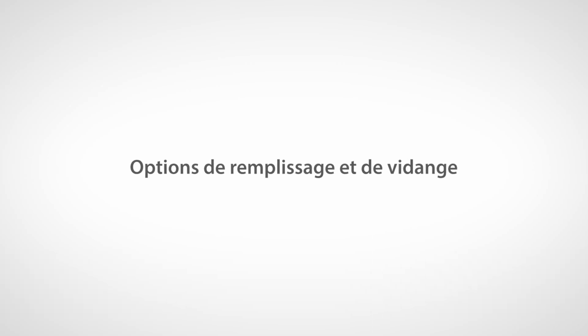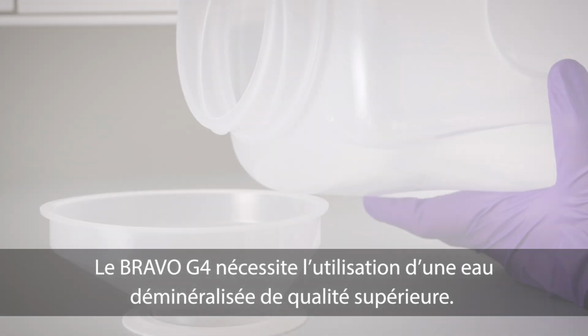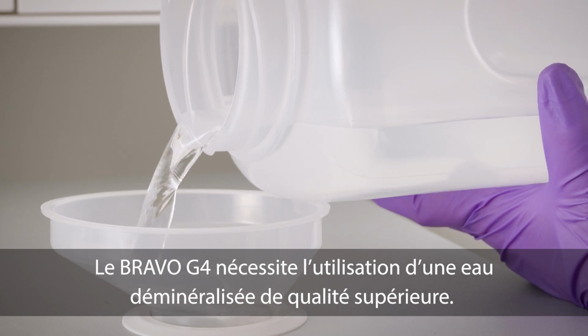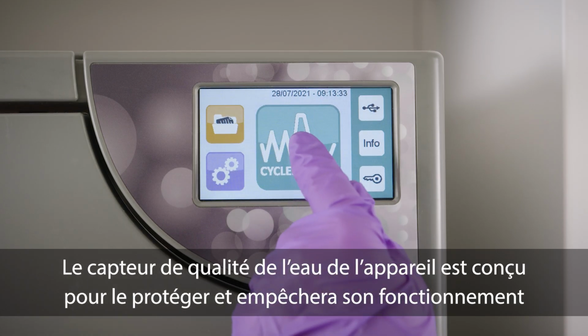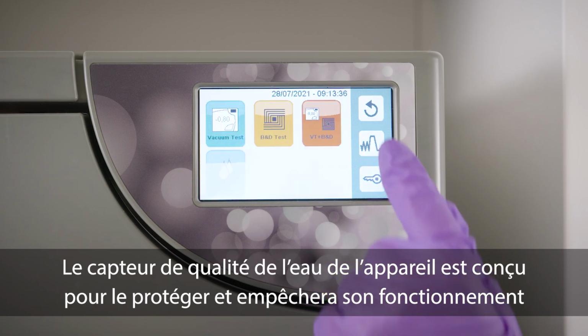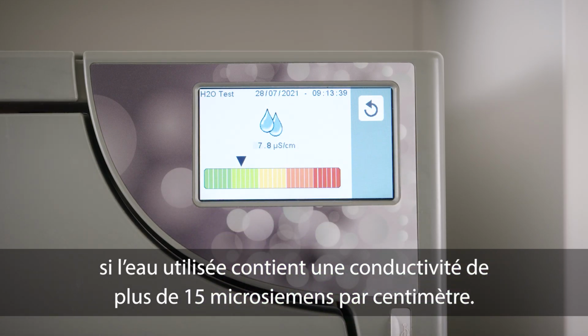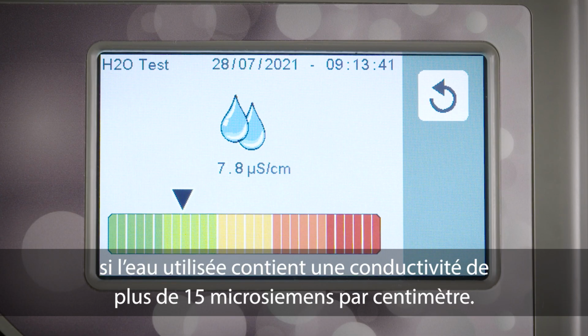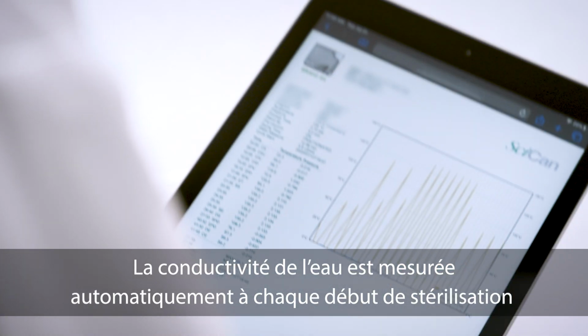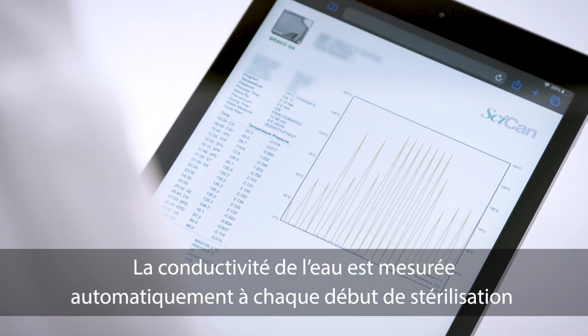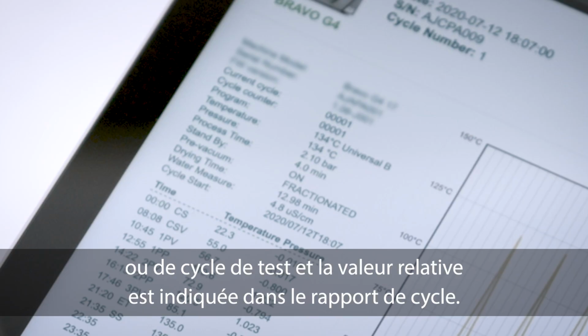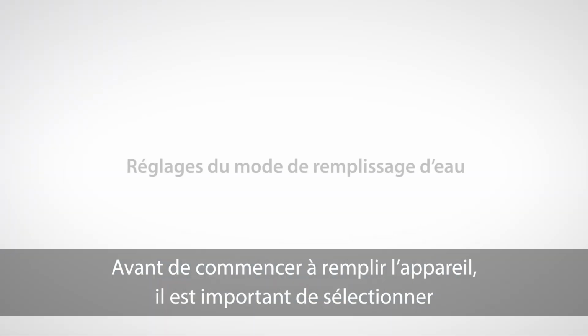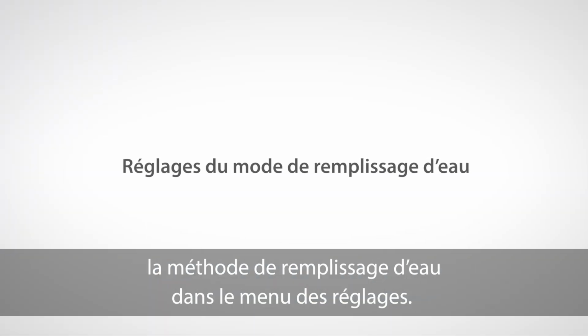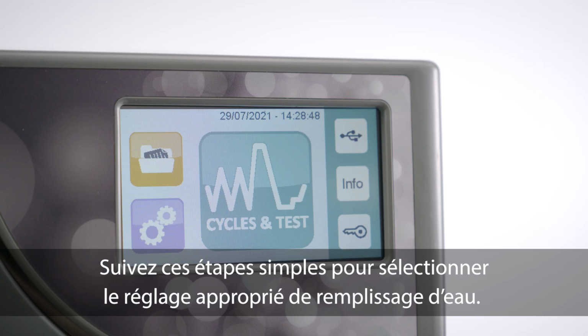Filling and draining options. The Bravo G4 requires high-quality demineralized water. The unit's water quality sensor is designed to protect the unit and will not allow it to function with water that has a conductivity of more than 15 microsiemens per centimeter. Water conductivity is automatically measured at the start of each sterilization or test cycle, and the relative value is indicated in the cycle report. It is important to select the water filling method in the settings menu before you begin filling the unit. Follow these simple steps to select the correct water filling setting.